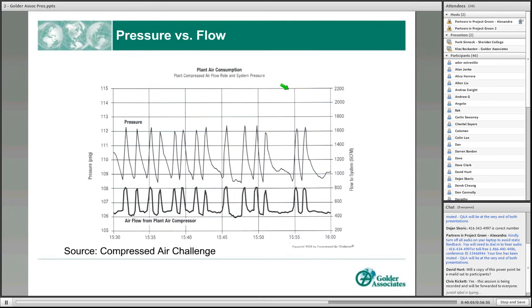Just to go back to the technical aspects of this plant with 3 compressors, this picture is actually courtesy of a compressed air challenge in the US. It shows the top curve indicates the pressure monitored over a period of about half an hour, and the curve below in bolder font is the actual airflow into the plant.